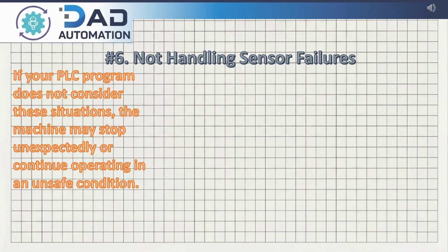For example, imagine a pneumatic cylinder that moves a product from one station to another. When the cylinder extends, the PLC expects the extended position sensor to turn on. But what happens if the sensor is faulty or the cylinder gets stuck halfway? A beginner's program may keep waiting forever for the sensor signal. As a result, the machine sequence freezes and production stops.